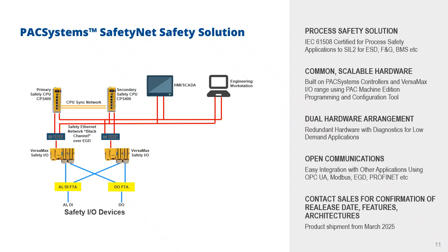So the CPU can be simplex or redundant, but the I/O has to be redundant, and that's not for availability reasons. The reason we have the redundant I/O is for the diagnostics we need. So if any single I/O point failed, then we can detect that, and then we can decide whether we want to trip the plant or go to some other state in order to control the way the plant works. So again, the requirements of the actual plant and what's required there for the operation, that would come from your functional safety assessment. Now, normally a safety system operates independently. There may be a HMI SCADA involved so that we can have monitoring of what's going on.